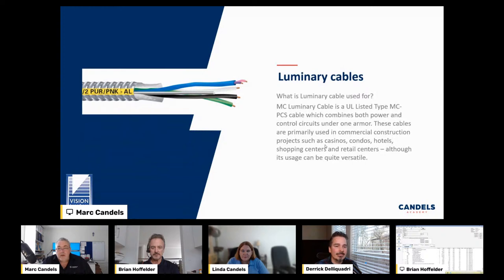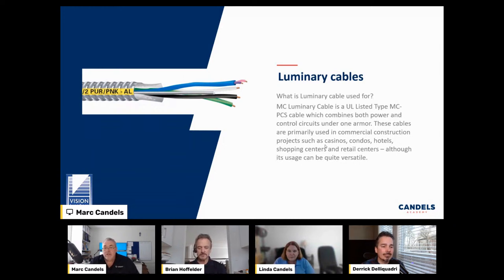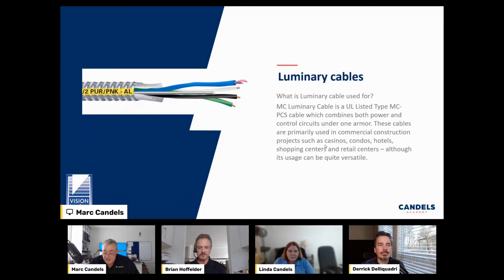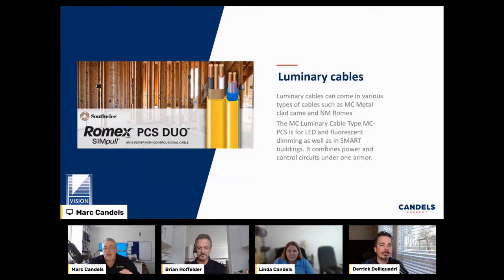The MC luminary cable type combines both power and control circuits under one armor. These cables are primarily used in commercial construction — casinos, hotels, shopping centers — mainly for architectural lighting where you want to change zones and controls. There's also an NMB or Romex-type luminary cable used in smart buildings. Southwire makes a product called PCS Duo Cable; other companies call it luminary. They all have their own acronym, but it's pretty much the same cable.